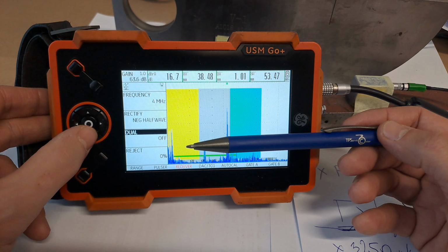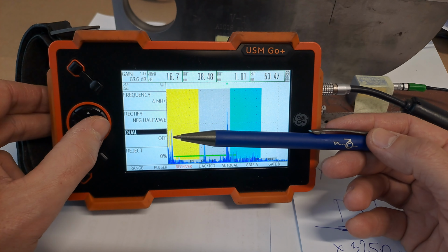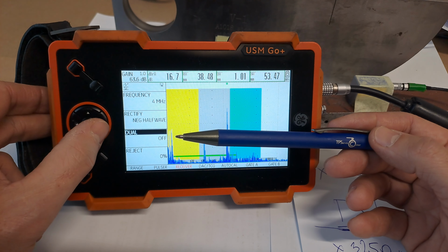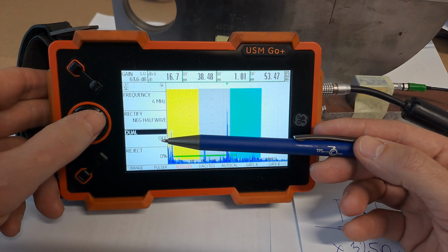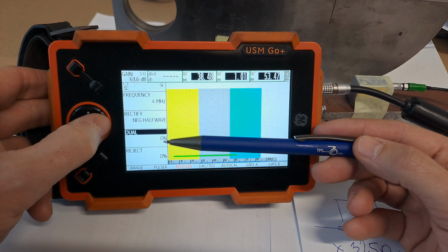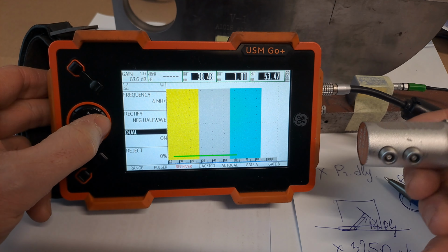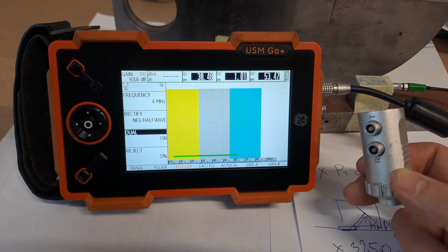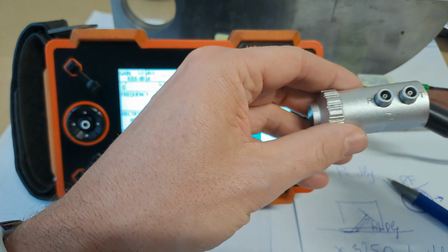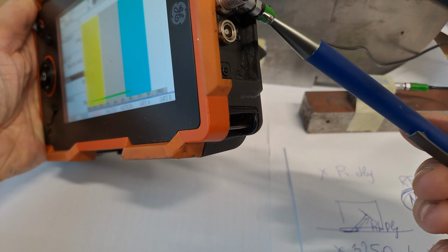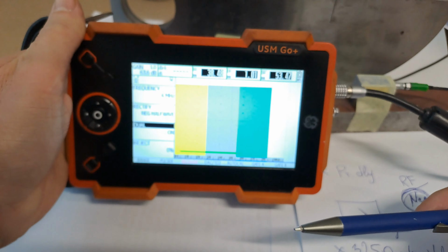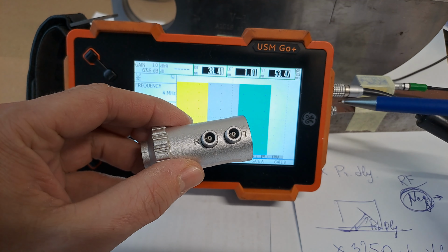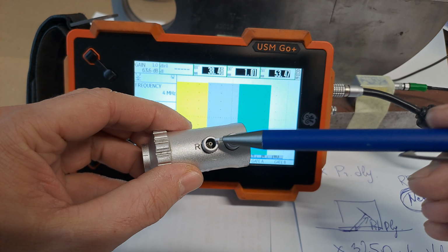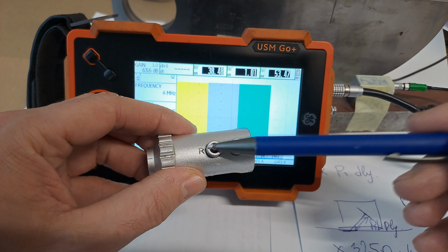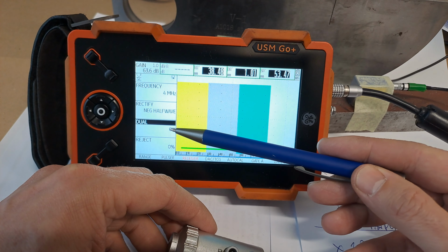Now, another thing about the receiver is dual. There are 3 settings. Dual is on, off and through. So I'm going right, it's on. The dual setting is for this probe, because for this probe we have transmitter and receiver, as well as here transmitter and receiver. So you should check that this goes in here, this goes in the right place. And if you have this for working, you have to put dual on.